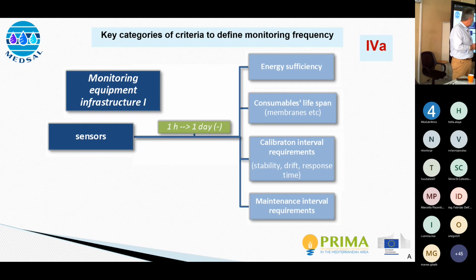You also need to take into account the consumables lifespan - the membranes and electrolytes in the sensors. For a pressure transducer or an electrical conductivity sensor, this isn't relevant because there are no consumables. But if you've installed a pH or ORP sensor, you have to be extra careful how often you monitor. There are two different things to consider.